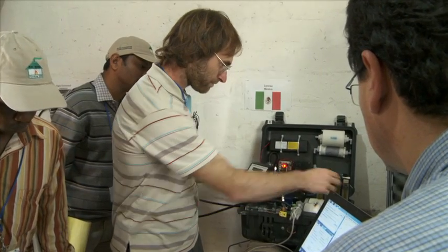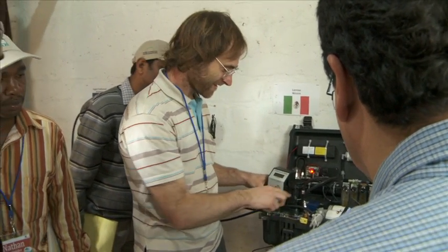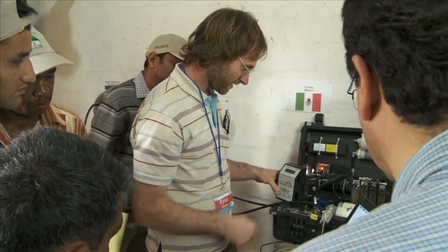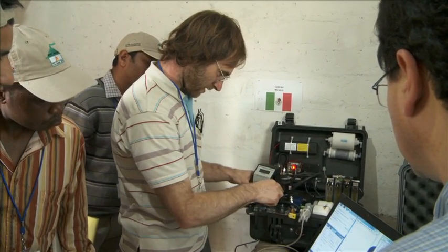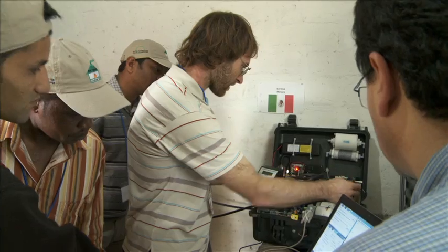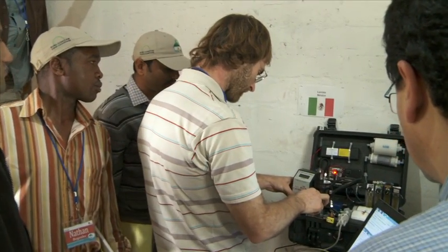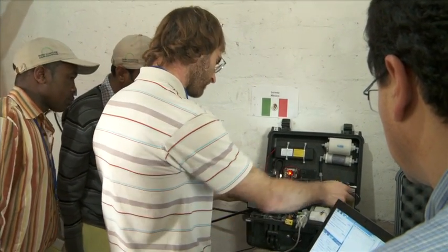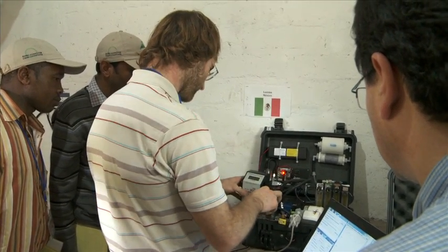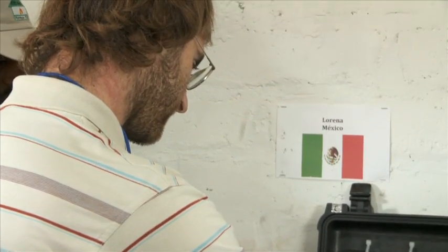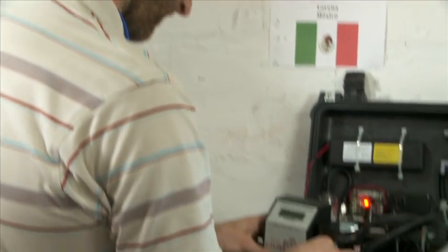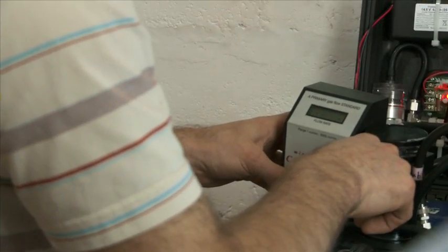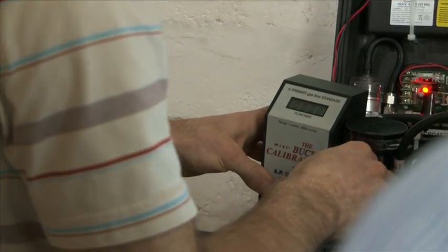You have the right amount of soap in there already? Yeah. We don't change the soap very often. What's the logic behind 1500? Because this cyclone requires a flow of 1500 in order to separate out and give a PM 2.5 cut. You're regulating the airflow? Yeah, that's a needle valve. How much do you need? 1500. So there, it's about right. That's good enough for now. 1490.